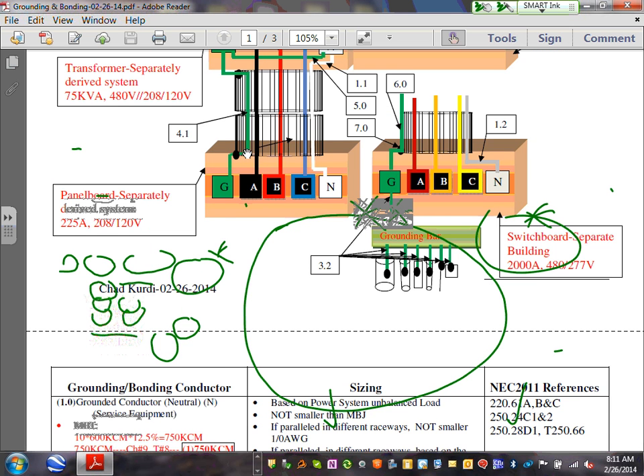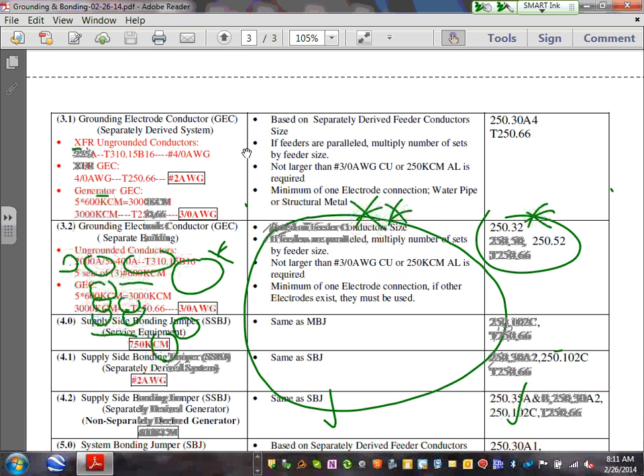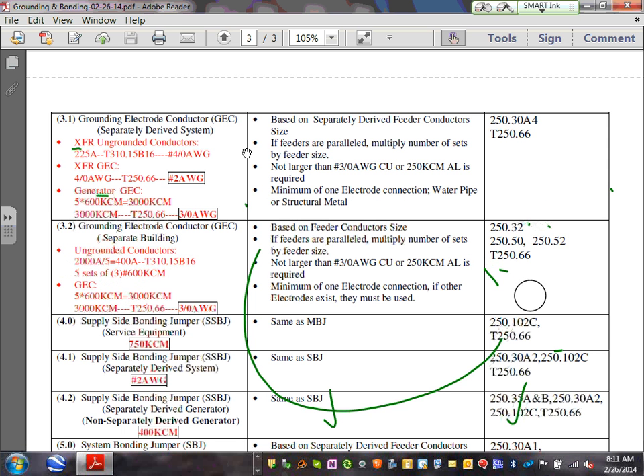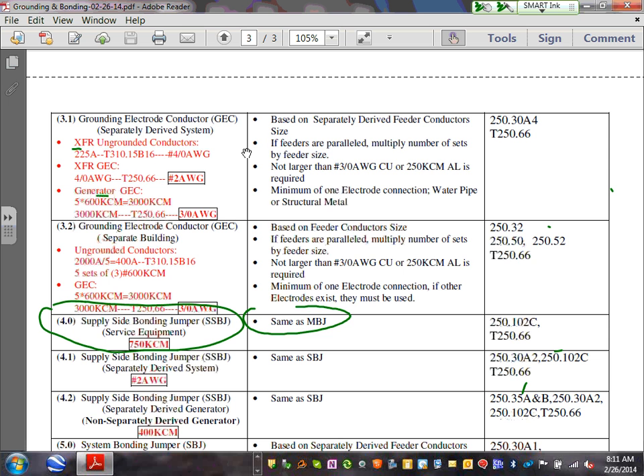Supply side bonding jumper. If you go to the system bonding jumper, it's 4.0. Supply side bonding jumper, bonding the conduits. Can you guys see that? So, when you go to 4.0 right here, very simple, very easy. If you go to the same switch gear, the 4,000 amp switch gear that you have here, and look at what this will tell you. 4.0, very easy. Can you see how to size it? It says main bonding jumper. So it says size it the same as the main bonding jumper. Any comments, guys? Any questions? Size it the same as the main bonding jumper. So it's 750. Any comments, any questions about 1.0, 2.0, 3.0, and 4.0?